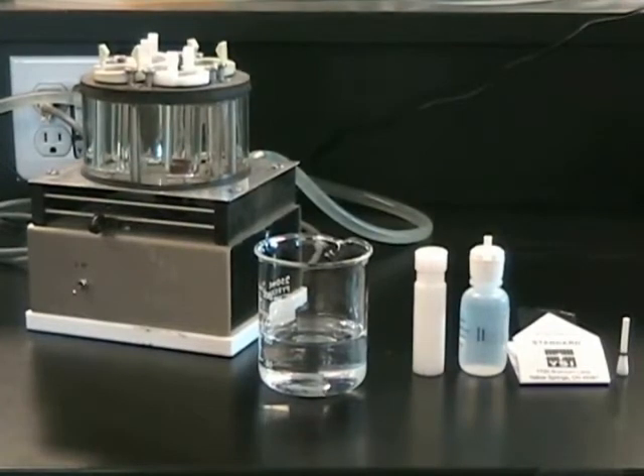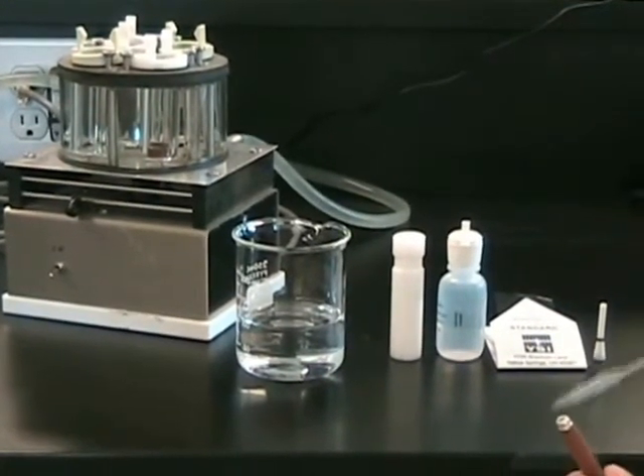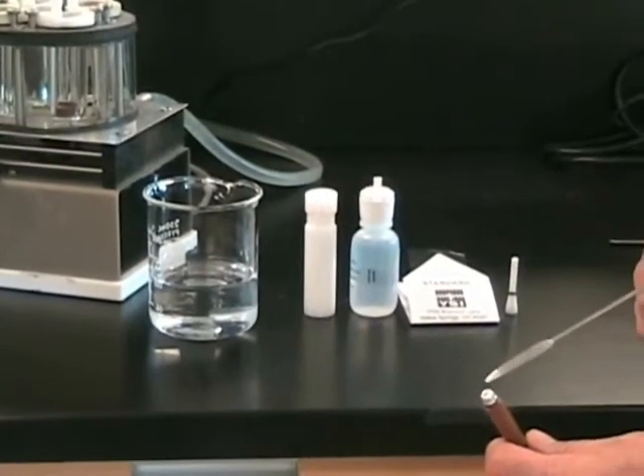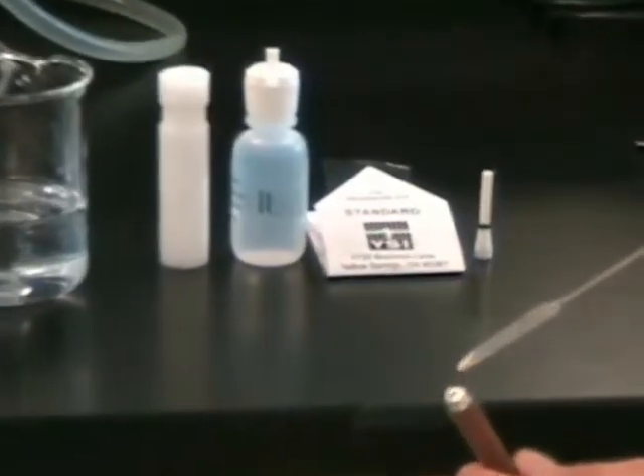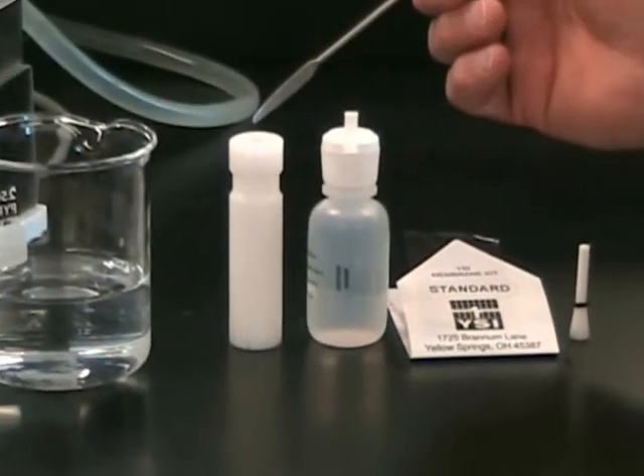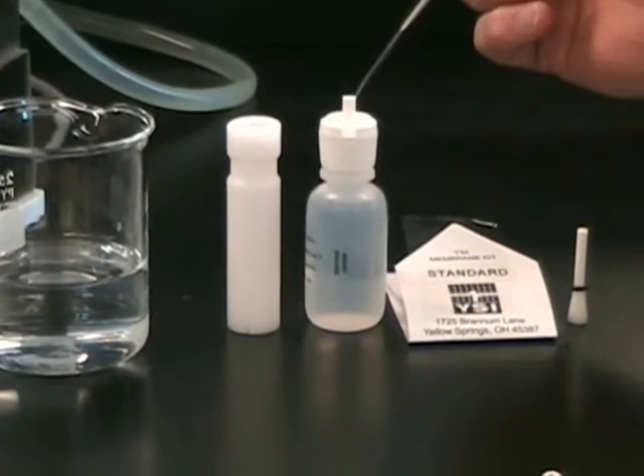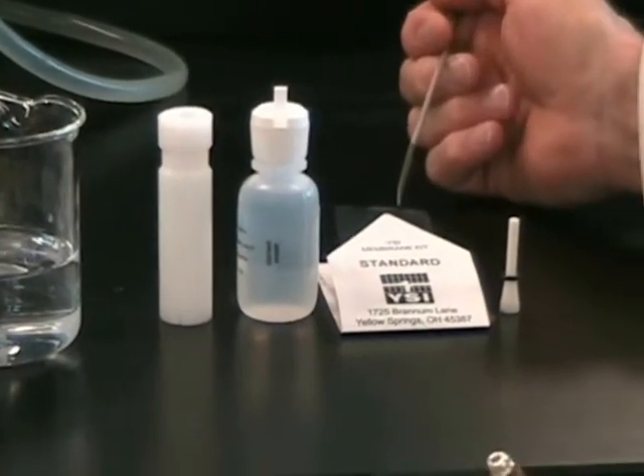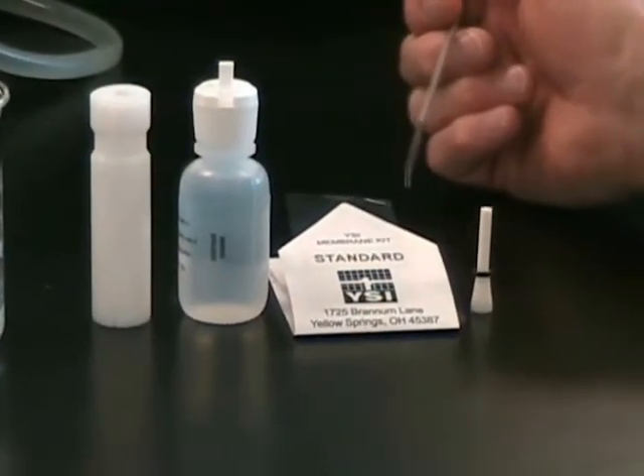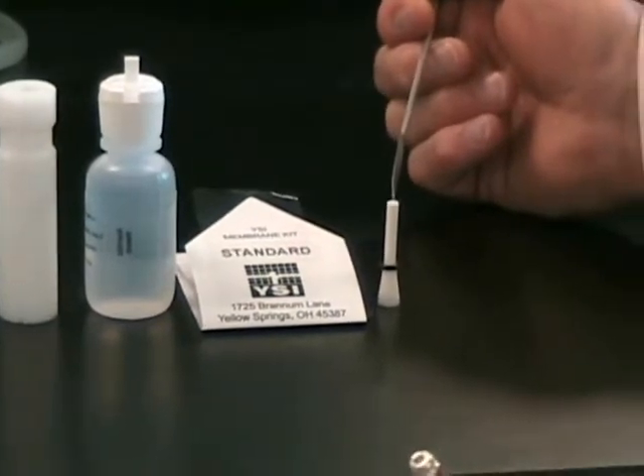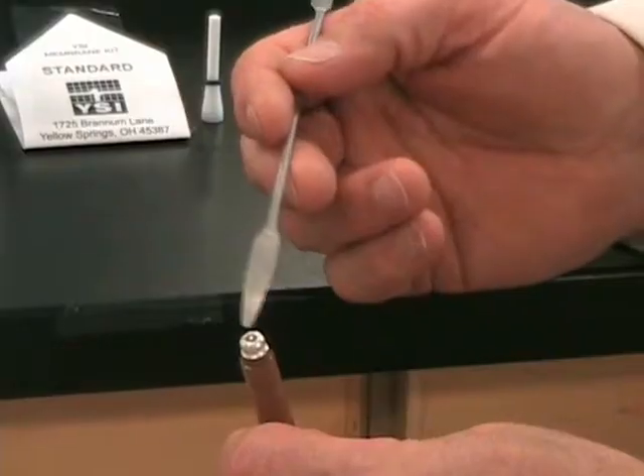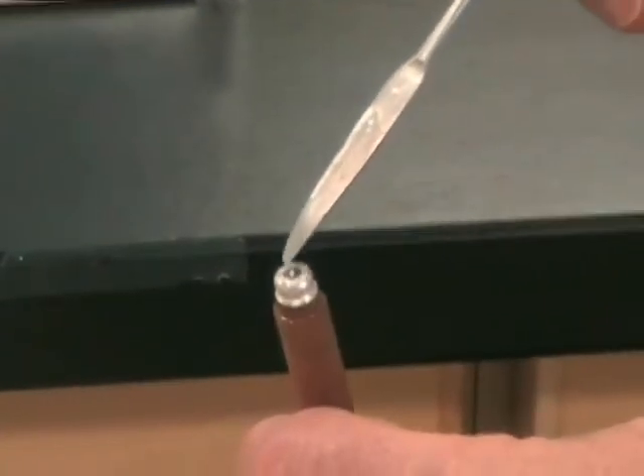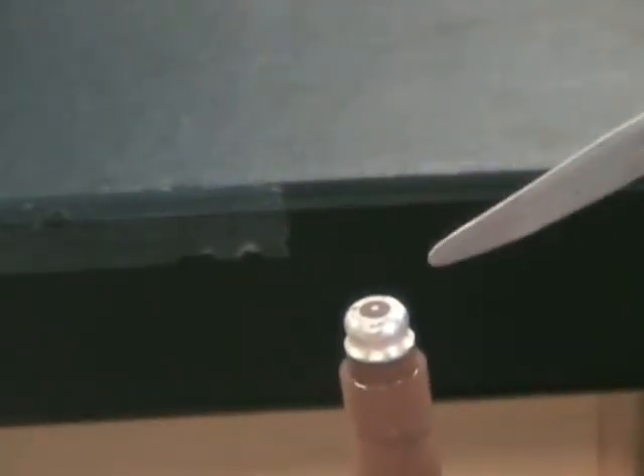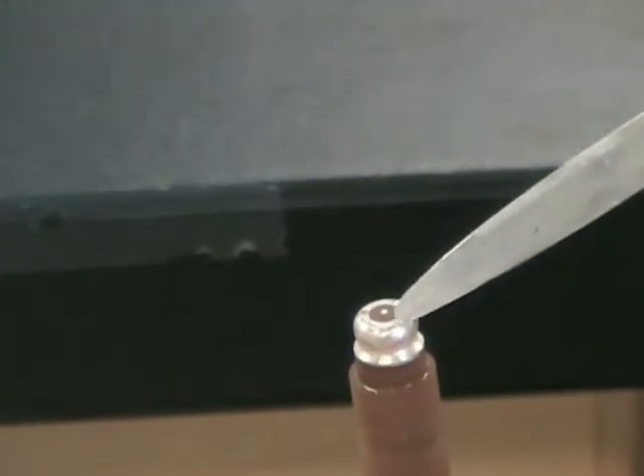Okay, let's have a look at the Clark oxygen electrode. It's made of 2 metals, silver and platinum. Over here we have the electrode body. We have the electrolyte to form the salt bridge, the membrane, the O-ring applicator, and the O-ring itself. We have a large piece of silver on the outside. We have a brown polymer that is inert, and in the center of the polymer we have the platinum wire.